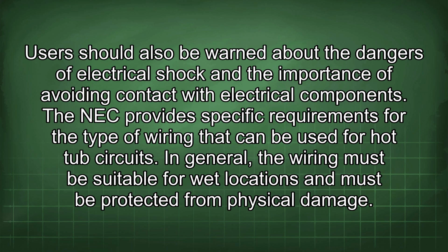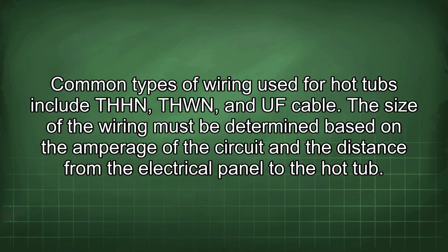The NEC provides specific requirements for the type of wiring that can be used for hot tub circuits. In general, the wiring must be suitable for wet locations and must be protected from physical damage. Common types of wiring used for hot tubs include THHN, THWN, and UF cable. The size of the wiring must be determined based on the amperage of the circuit and the distance from the electrical panel to the hot tub.